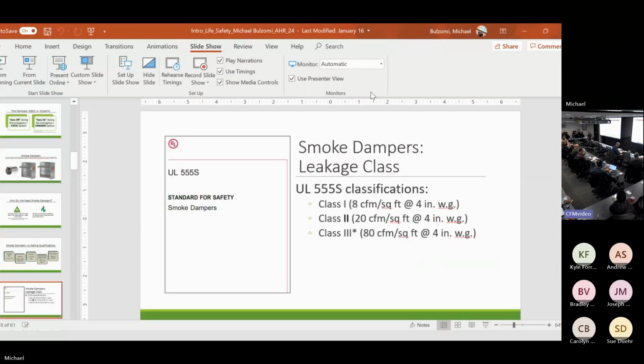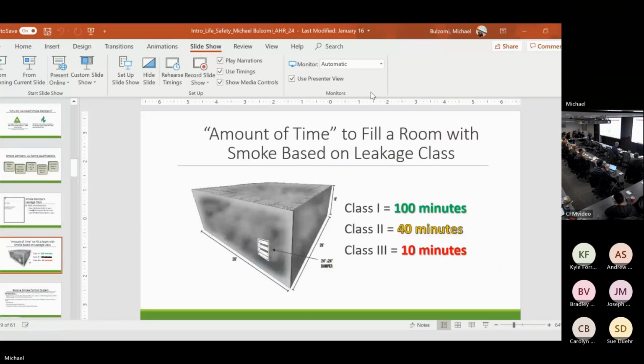So what is leakage class? Here are definitions from UL 555S. That's class 1, the tightest and lowest leakage. That's 8 CFM per square foot. Class 2, the minimum building code requirement, 20 CFM per square foot, so 2.5 times more leakage, versus class 3, which was 80 CFM per square foot. Let's throw all this out the window. What does this really mean?